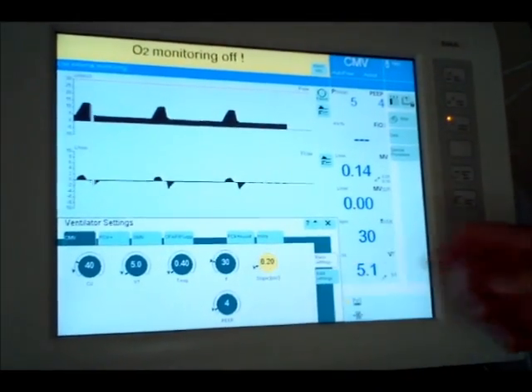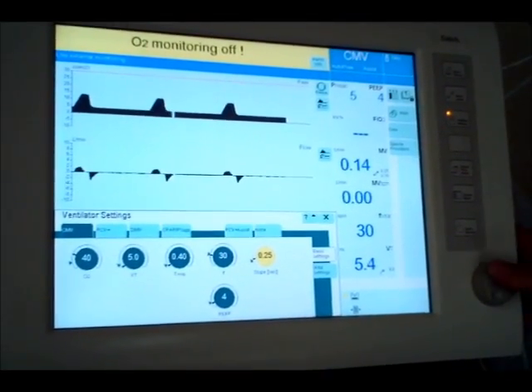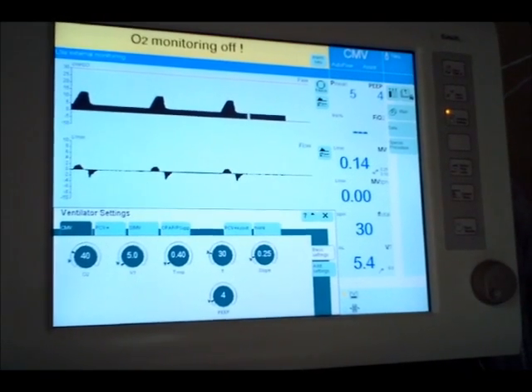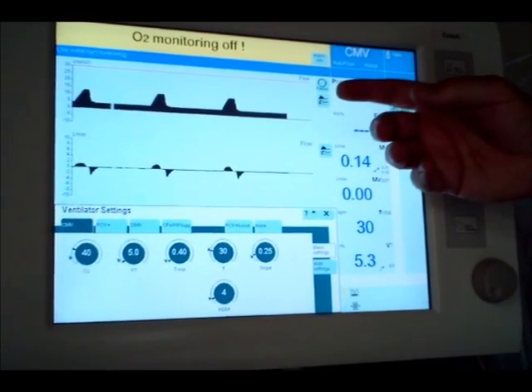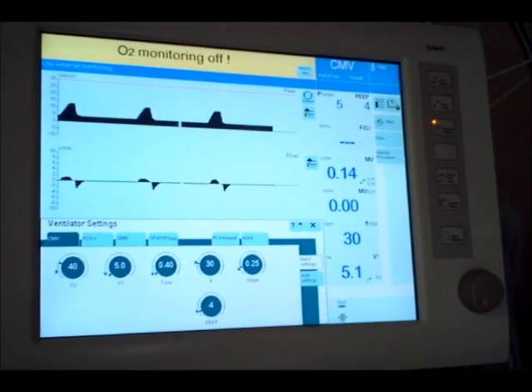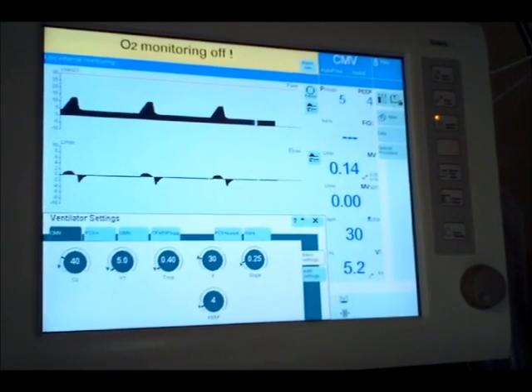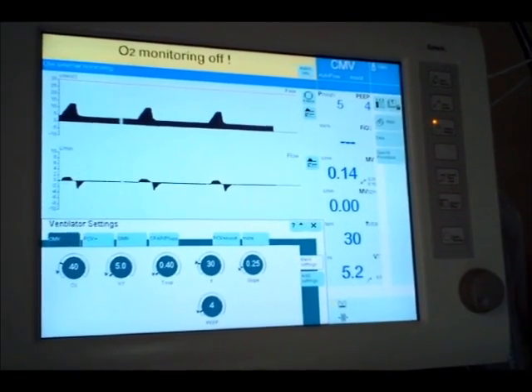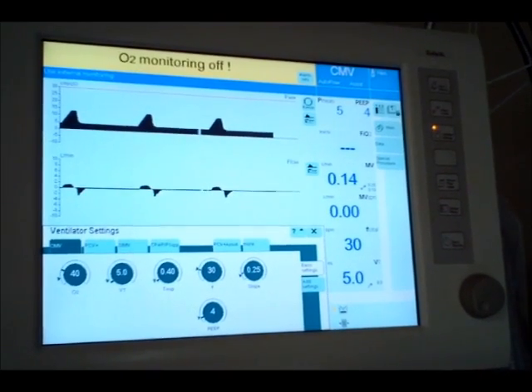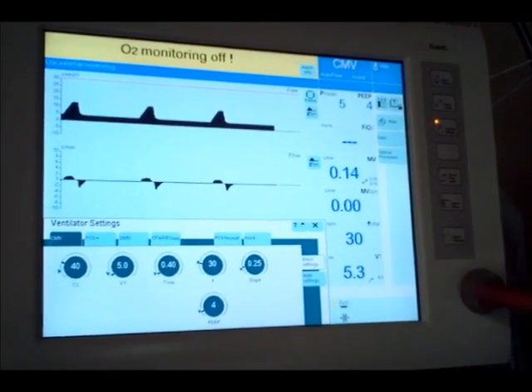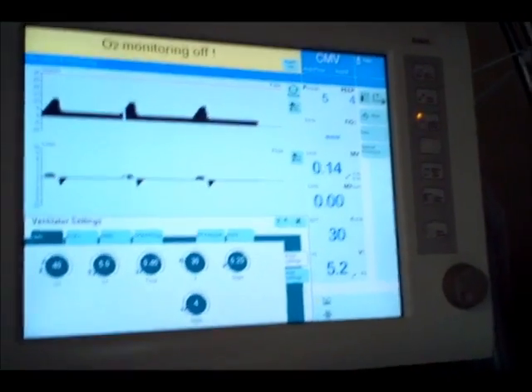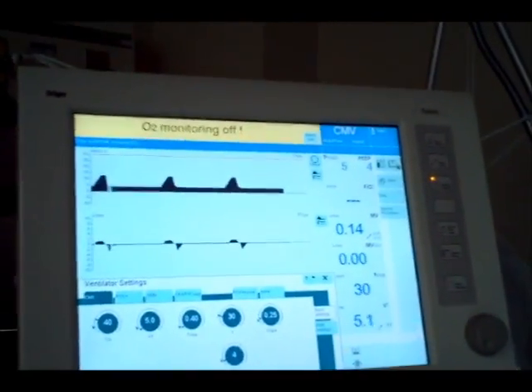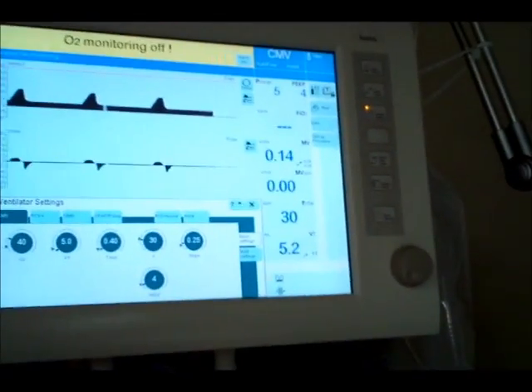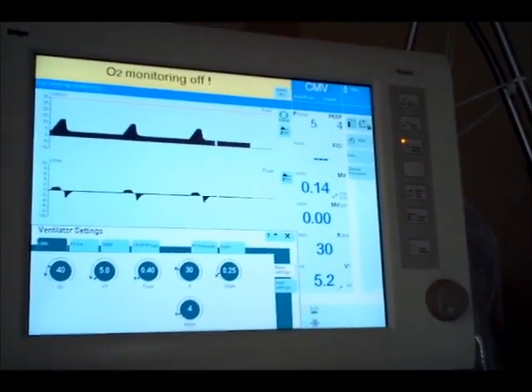Well, on the Babylog, we'd use inspiratory time, but now we have a slope function we can use. Let's back that off. Let's make it a little bit more gentle. And we get a little bit less of a square top on it there, because we don't hit that peak pressure as soon. Probably if you do that, you want to check your tidal volume. Right down here is our tidal volume number. We're still getting our tidal volume of 5 or around 5. So that's how I'll handle the slope one there. Remember, you don't want to set your slope any longer than your inspiratory time.